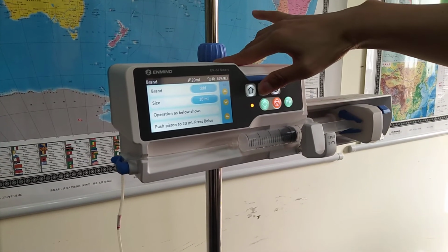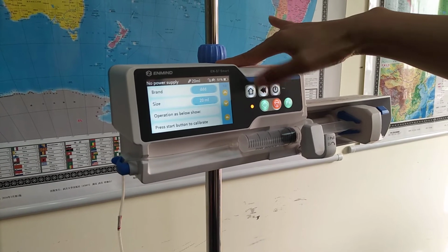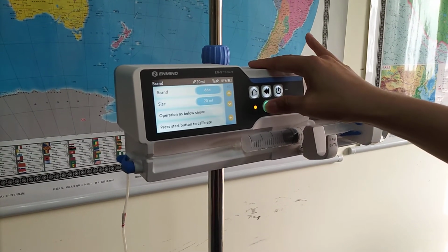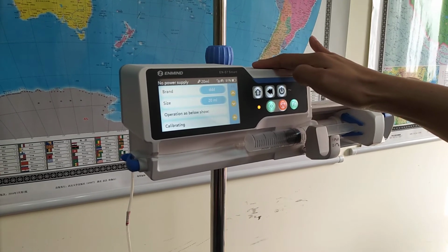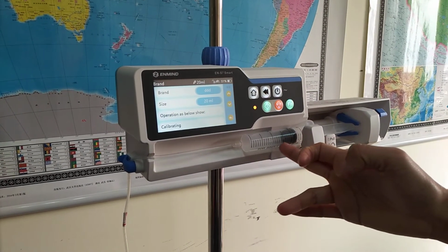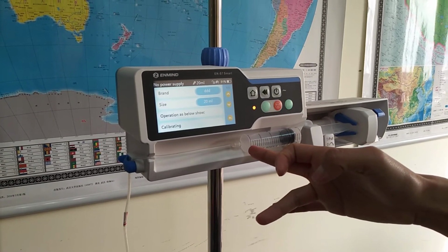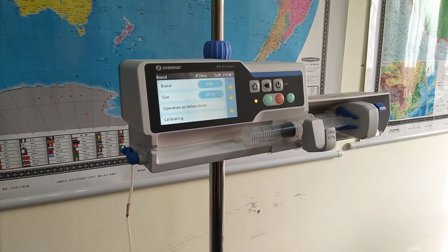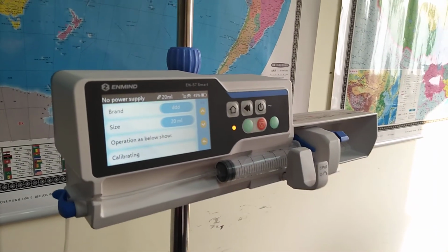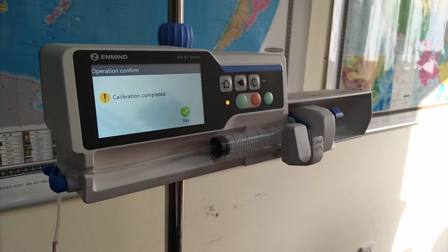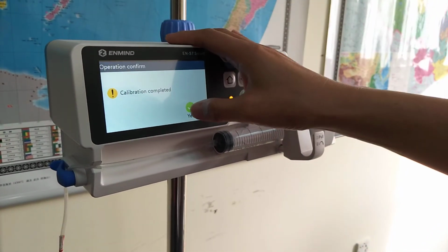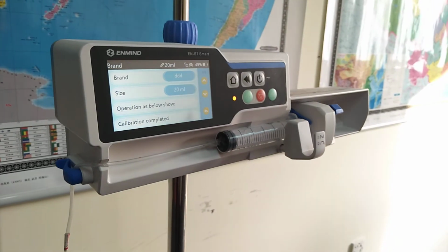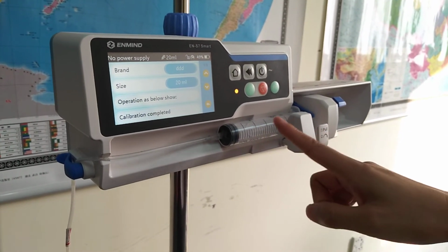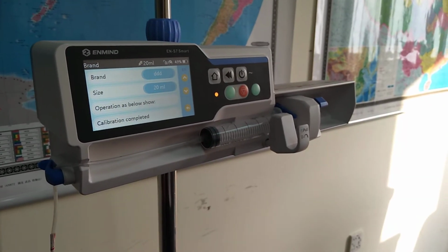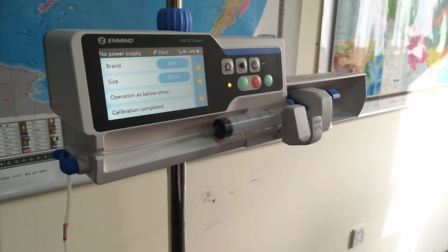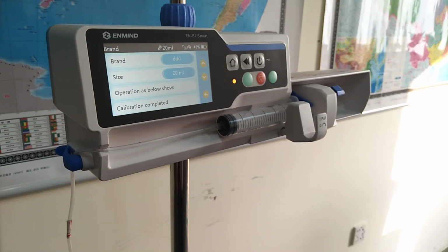Now we can do bolus to remove the air bubble. Now we just click this Start button to do the calibrating. So you can see it's running. When it reaches the end, the calibration is completed. So the calibration is completed now. This is a 20 milliliter syringe. If you need to do other size syringes, please follow the above steps. Repeat the above steps.